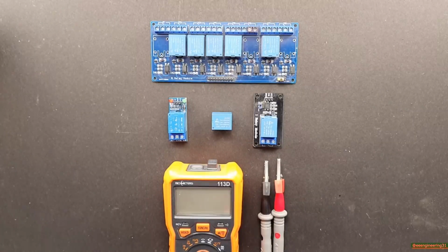The maximum current the switch contacts can handle is shown. If the markings read 12 volt DC 3 ampere, that indicates a 12 volt coil intended to be driven with DC power, with switch contacts capable of switching 3 amps.